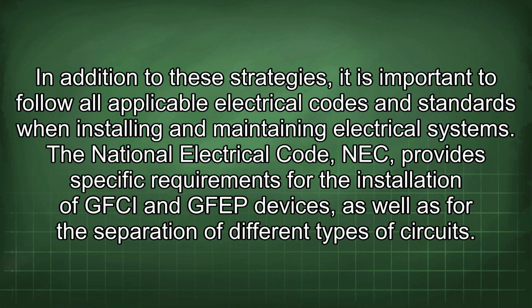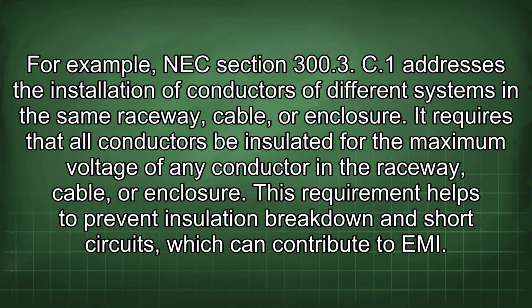In addition to these strategies, it is important to follow all applicable electrical codes and standards when installing and maintaining electrical systems. The National Electrical Code (NEC) provides specific requirements for the installation of GFCI and GFEP devices, as well as for the separation of different types of circuits. For example, NEC Section 300.3(C)(1) addresses the installation of conductors of different systems in the same raceway, cable, or enclosure. It requires that all conductors be insulated for the maximum voltage of any conductor in the raceway, cable, or enclosure.